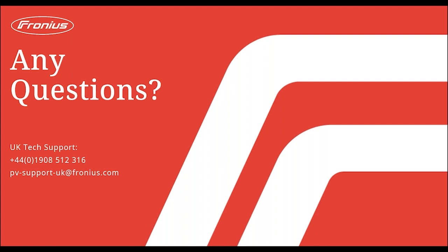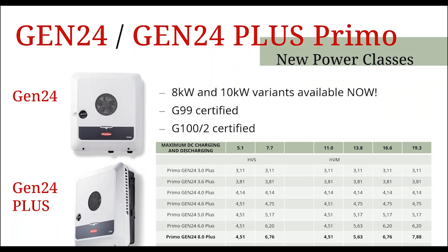If I jump back to the page where we had the power classes of the battery, you'll see that different batteries have different power outputs. So the smallest unit with the smallest inverter is 3.11 kilowatts of power. You can then obviously contribute also with some solar energy if it's during daytime up to the power class of the inverter. So the best solution would be a 10 kilowatt Gen24 with a good sized battery and then also with solar connected to it.